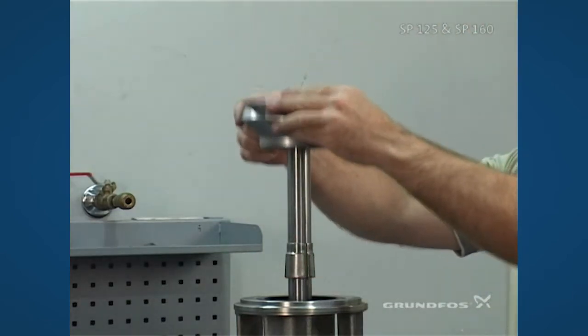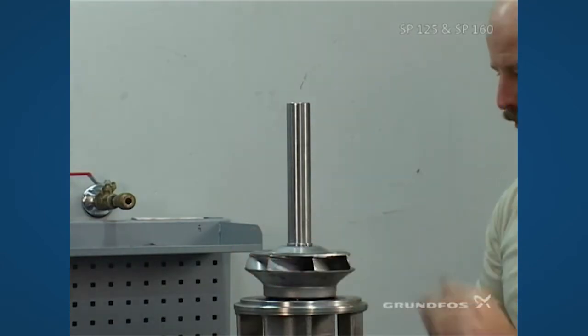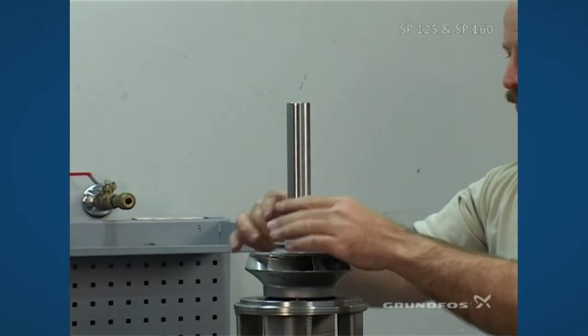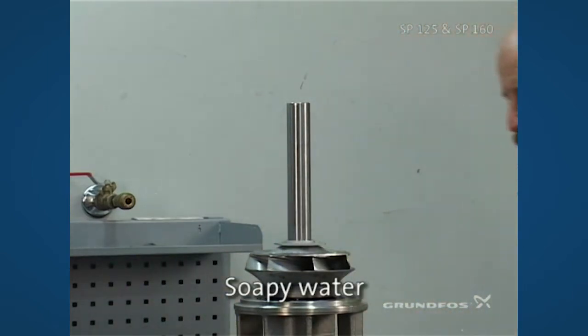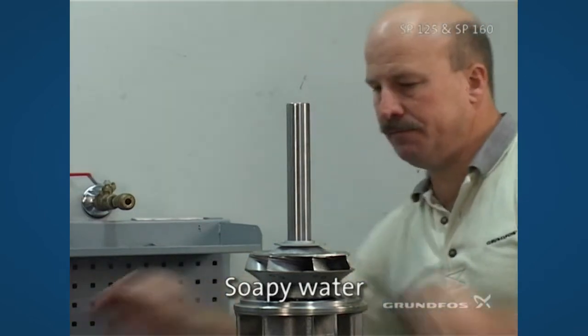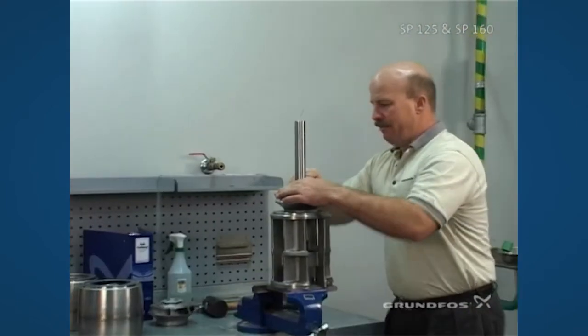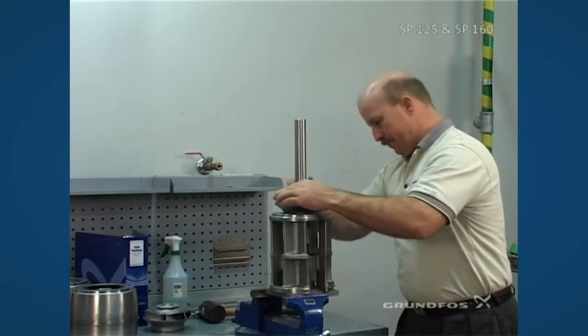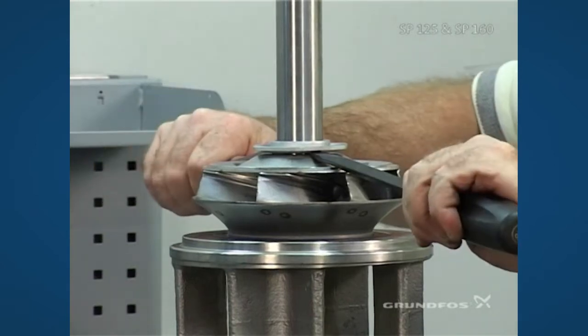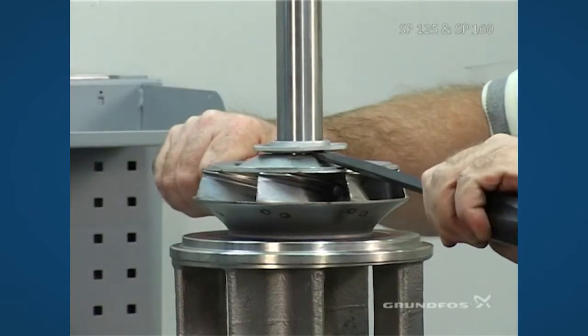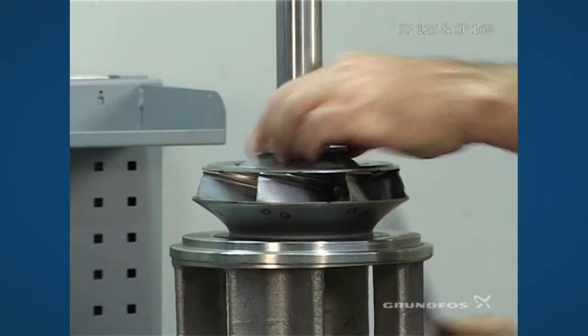Then you can add the impeller and the split cone nut. We want to make sure we have soapy water up where it seats and then firmly seat it all the way down. At this point, we want to take our two screwdrivers and make sure that the cone is pulled all the way up in through the impeller.